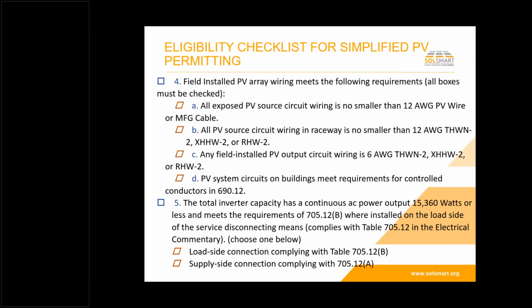Most of you are probably not electrical people, but the people that are electrical really care about those things, and they should. We're really not going to have any combiner boxes, so C really doesn't come into play very much. And then D, PV system circuits meet the requirements for controlled conductors that are part of rapid shutdown. So we're going to make sure that the system is a compliant rapid shutdown system, which again is a very common compliance requirement, and the installers and the products are readily available out there.